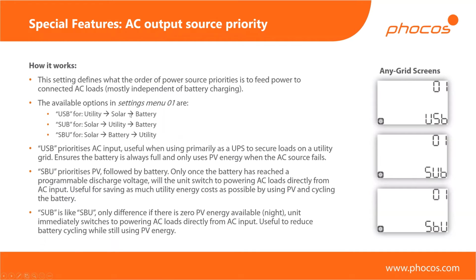So let's start off with the first one, the utility solar battery. This is the scenario where solar isn't actually that important to you, or you might have a very small PV array just to keep your battery topped up. But basically, the reason you're using the AnyGrid is to handle scenarios where the grid fails. So in that case, guaranteed power is more important than the cost of power, for example. So you want to prioritize the grid or the utility as a first priority. You'll use solar if the grid fails, and then battery to make up for it if you don't have enough solar power.